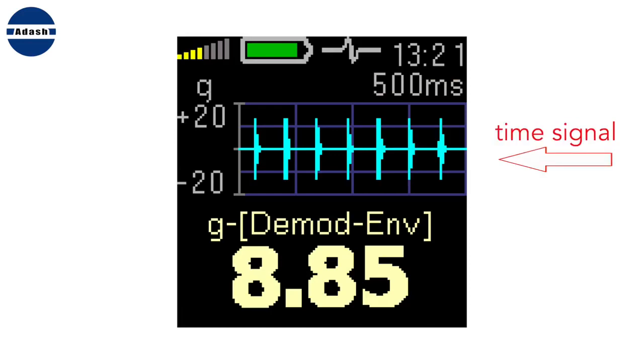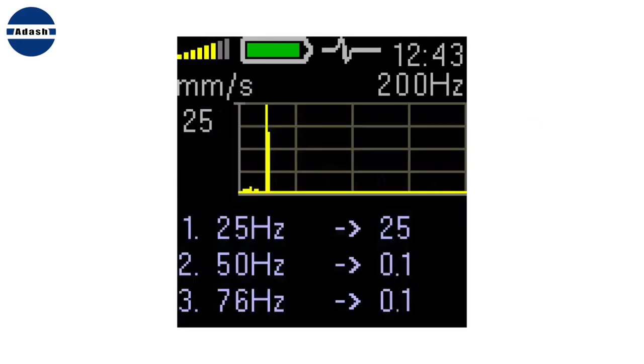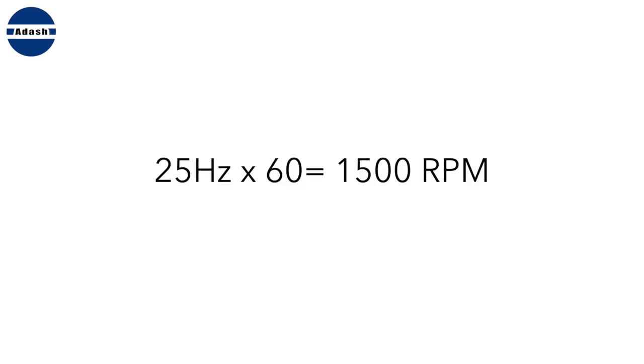You should find regular shocks there. If the velocity value is high, then you need to look at the spectrum screen. If the spectrum contains only one high line on the speed frequency, then the unbalance is the failure. For example, on this spectrum is only one high line on 25 Hz. When you multiply the 25 times 60, then you obtain 1500 rpm. If the speed is 1500 rpm, then unbalance is the failure.